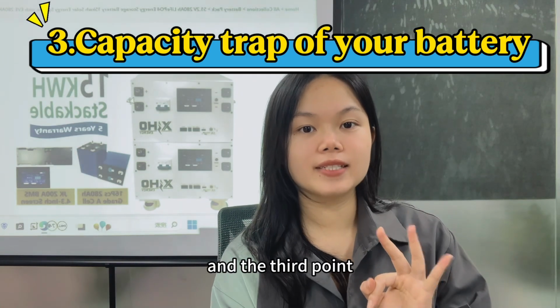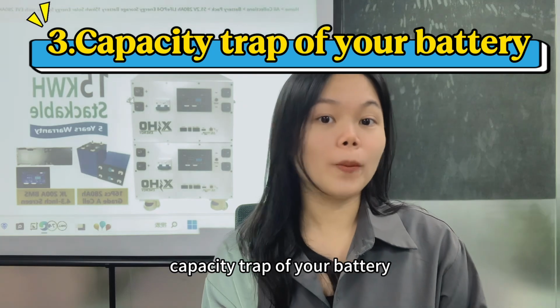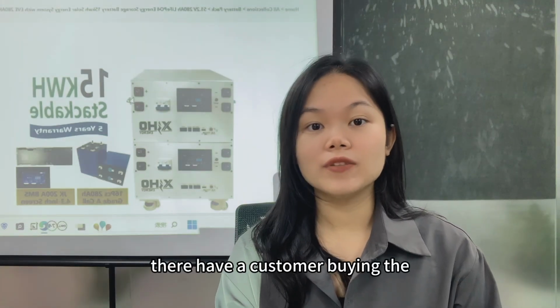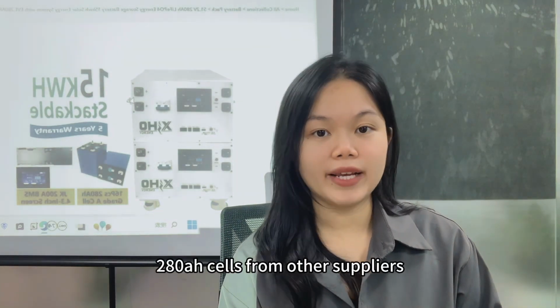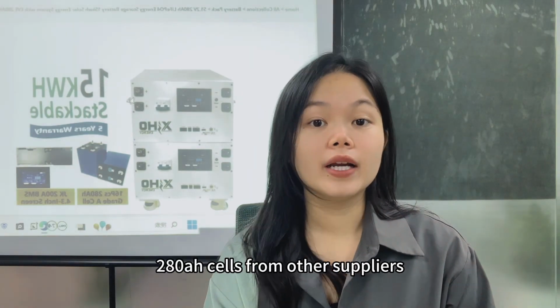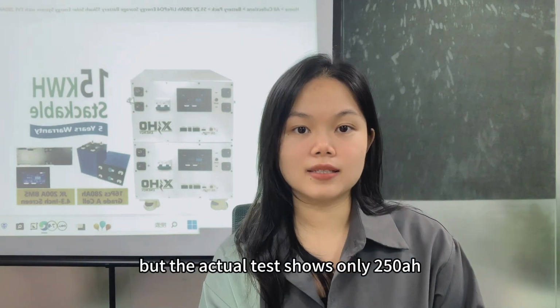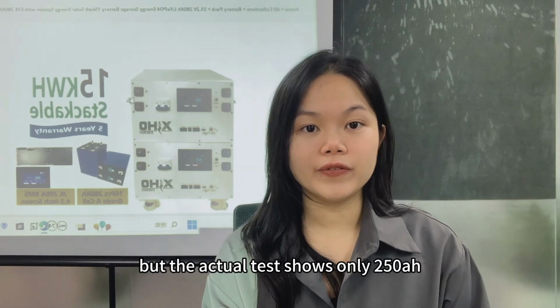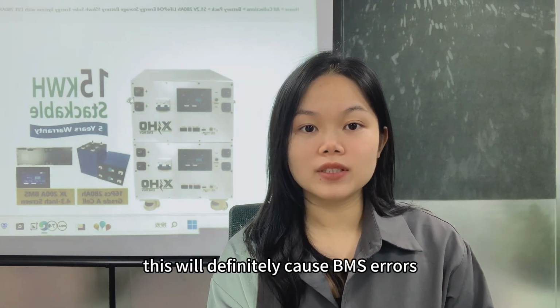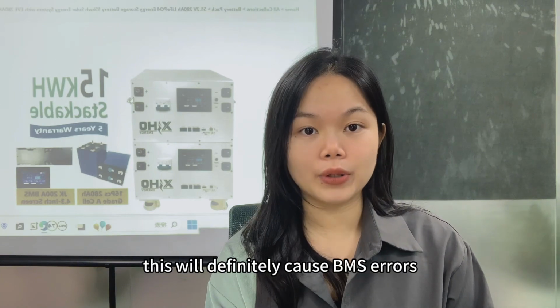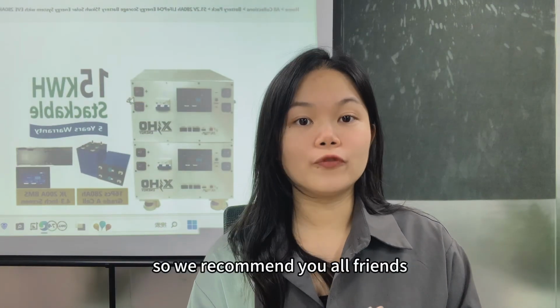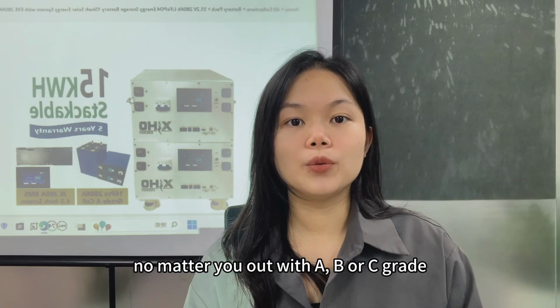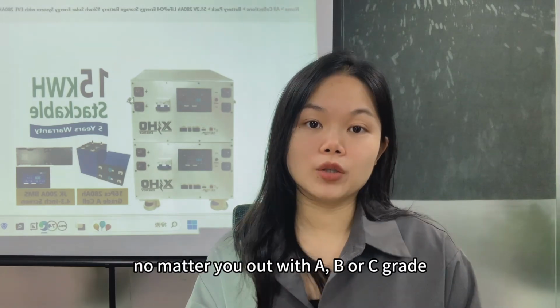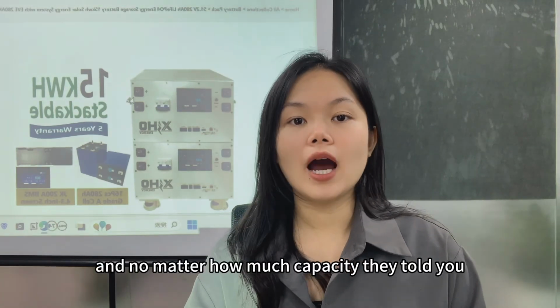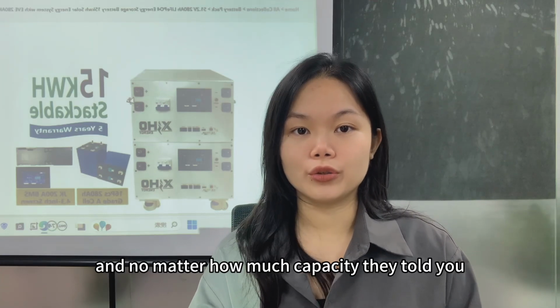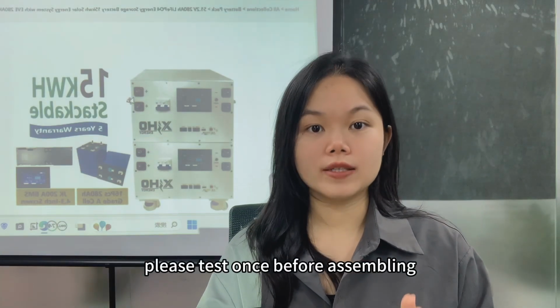And the third point, capacity check of your battery. We had a customer buying 280 ampere-hour cells from other suppliers, but the actual test shows only 250 ampere-hour. This will definitely cause BMS errors. So we recommend all friends, no matter whether you bought A grade or B grade or C grade, and no matter how much capacity they told you, please test once before assembling.